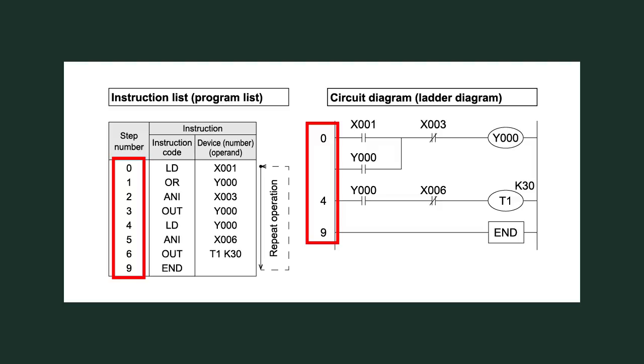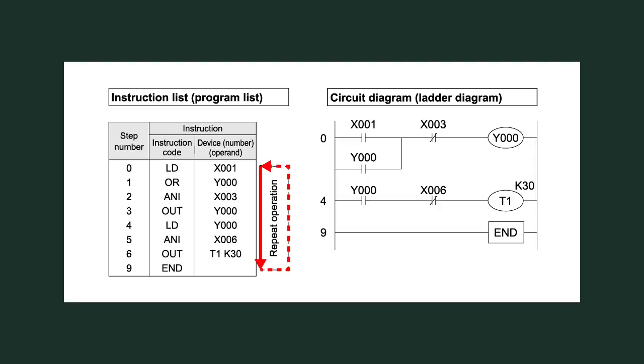The PLC's program capacity is fixed to a limited number of steps. The instructions are executed from step 0 to end, then it returns to step 0 and repeats continuously. This is called cyclic execution, and the time it takes to execute step 0 to end once is called the scan time.